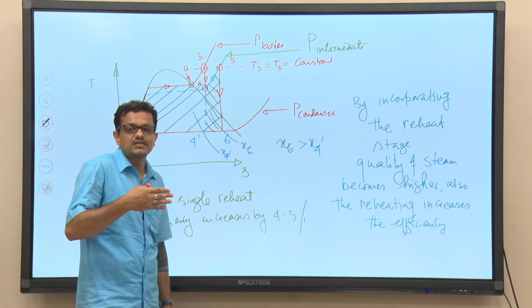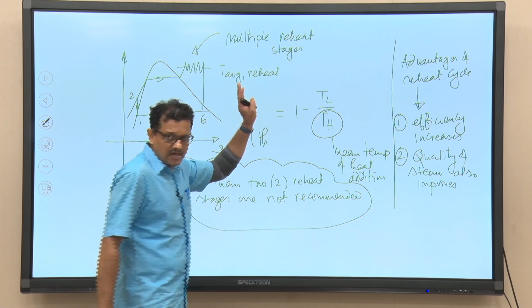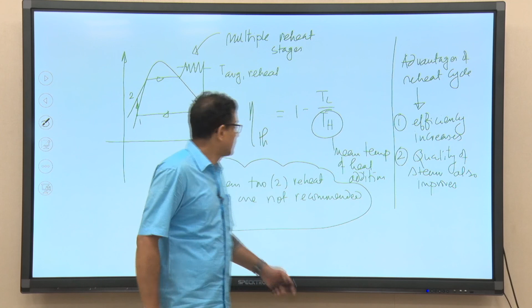Now, one important point I would like to discuss: we really cannot go beyond 2 reheat stages from the practical point of view. As I discussed, you can go up to 5, but it should be justified. With 5 reheat stages, the cost associated with installation as well as operation should be justified by the increase in efficiency that we are getting out of these 5 reheat stages. So, having a comparison cost analysis, it is observed that more than 2 reheat stages are not recommended.